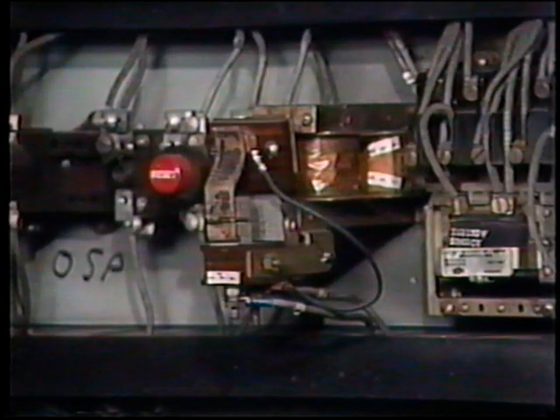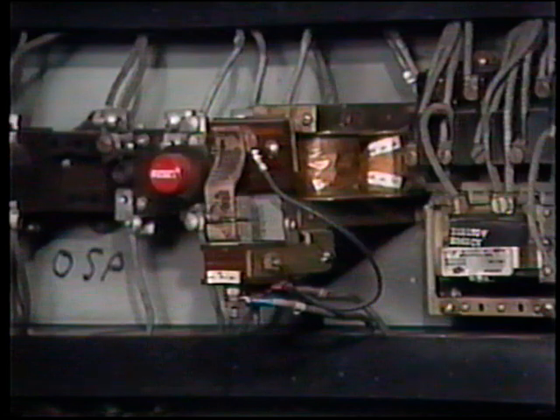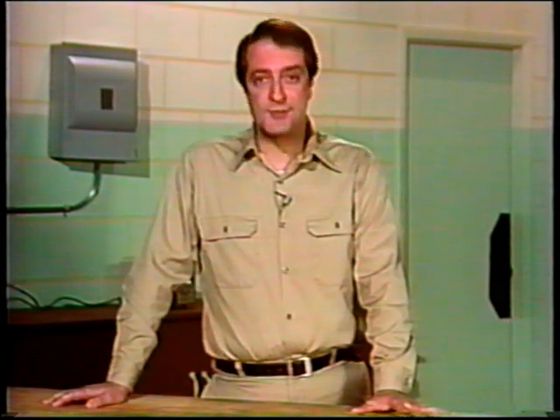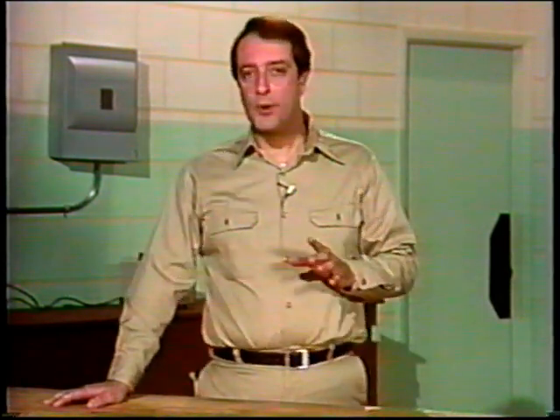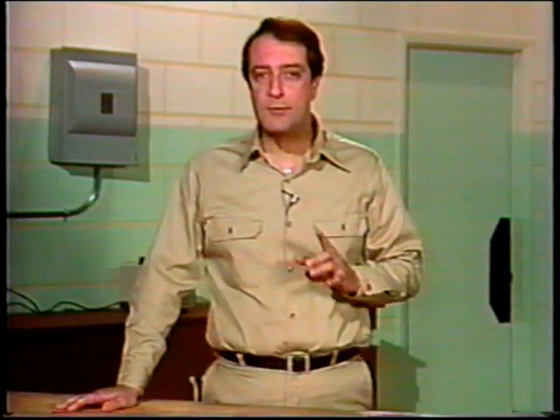Examine the operating coil of each relay. Look for any signs of overheating, such as damaged insulation. Once you've carefully cleaned and inspected the controller and have replaced any components necessary, have the controller energized, its tags removed, and return it to service. It's very important for you to properly maintain the synchronous motors and controllers in your plant. So before going any further, take the time to learn these preventive maintenance procedures.